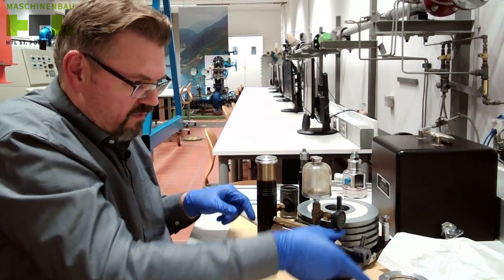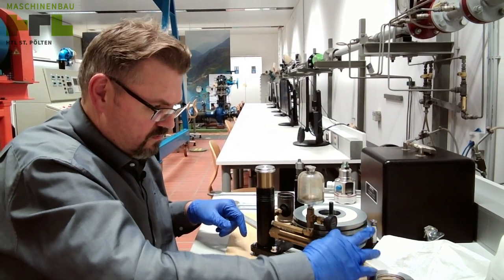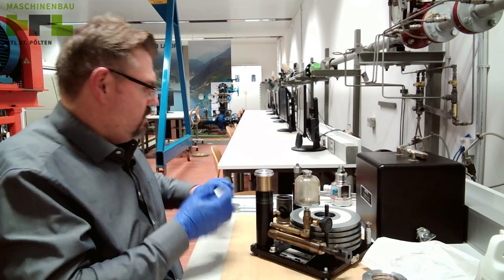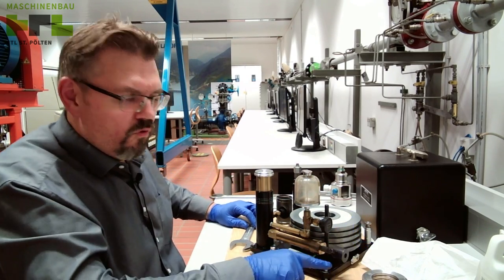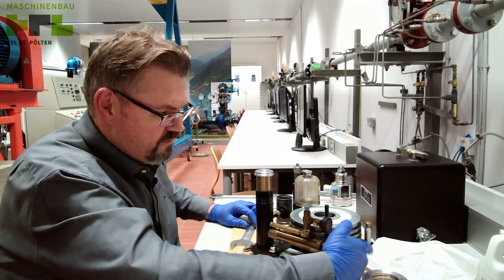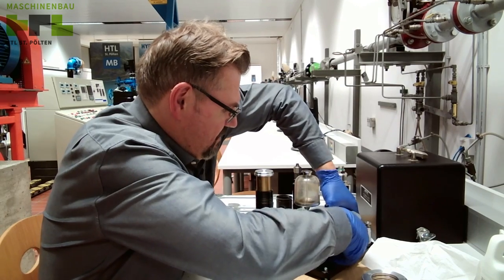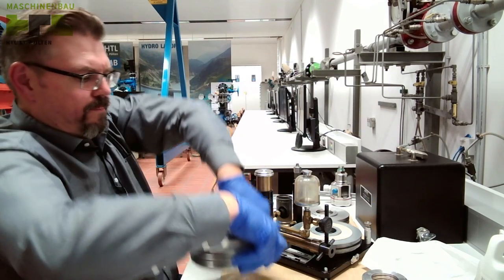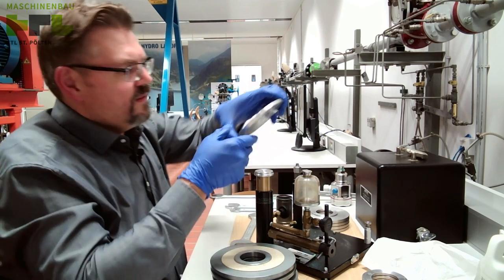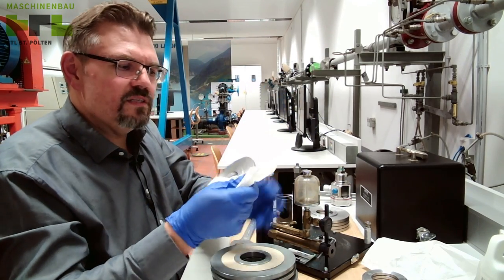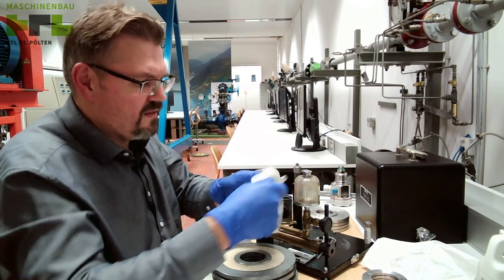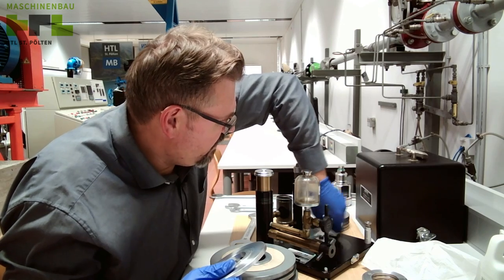I will put it in again here. Let's mount this all. That should be sufficient. And here I can now operate the piston inside the cylinder. I will move it completely in. Here, these are the big weights. This is the weight which is especially produced for this device. That's the calibration disk. Again, a little bit oily, so I will clean it.